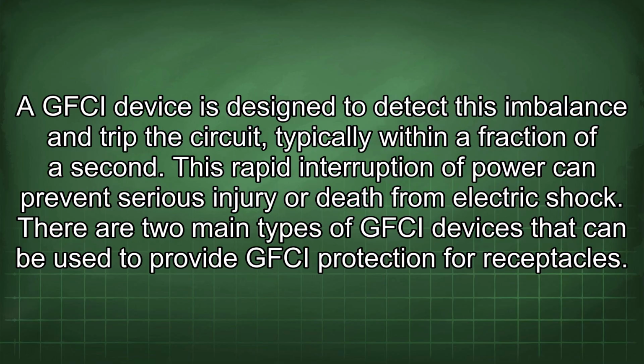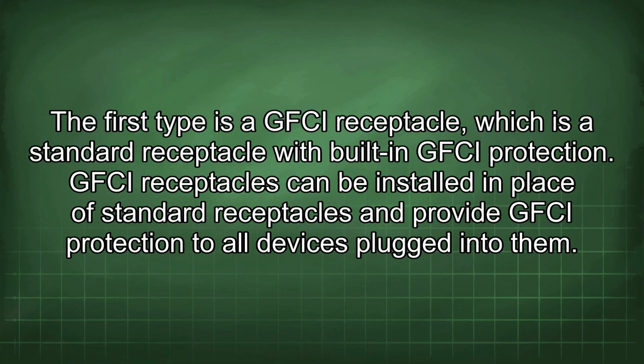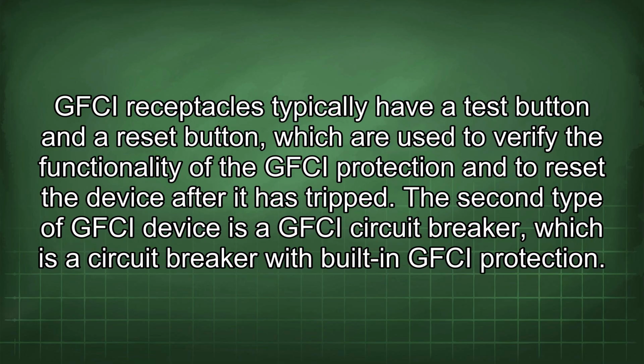There are two main types of GFCI devices that can be used to provide GFCI protection for receptacles. The first type is a GFCI receptacle, which is a standard receptacle with built-in GFCI protection. GFCI receptacles can be installed in place of standard receptacles and provide GFCI protection to all devices plugged into them. GFCI receptacles typically have a test button and a reset button, which are used to verify the functionality of the GFCI protection and to reset the device after it has tripped.